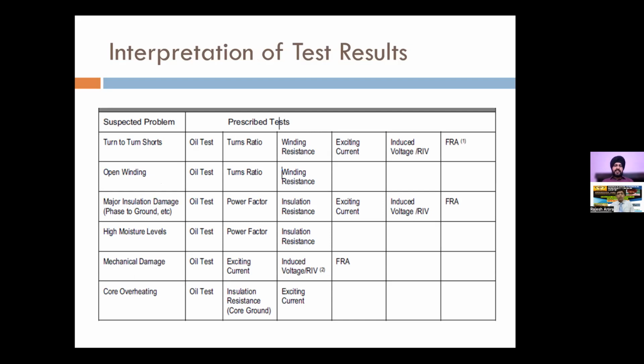Let us say there is a turn-to-turn short within the winding. Then oil test, turn ratio, winding resistance, exciting current, induced voltage, and FRA, all of these tests will indicate some problems. If our winding is open, then turn ratio and winding resistance will indicate some problem.